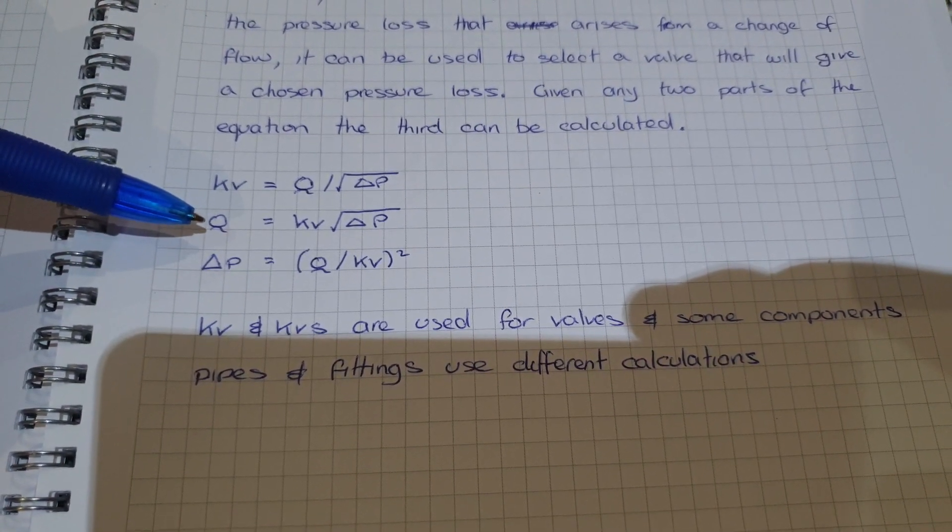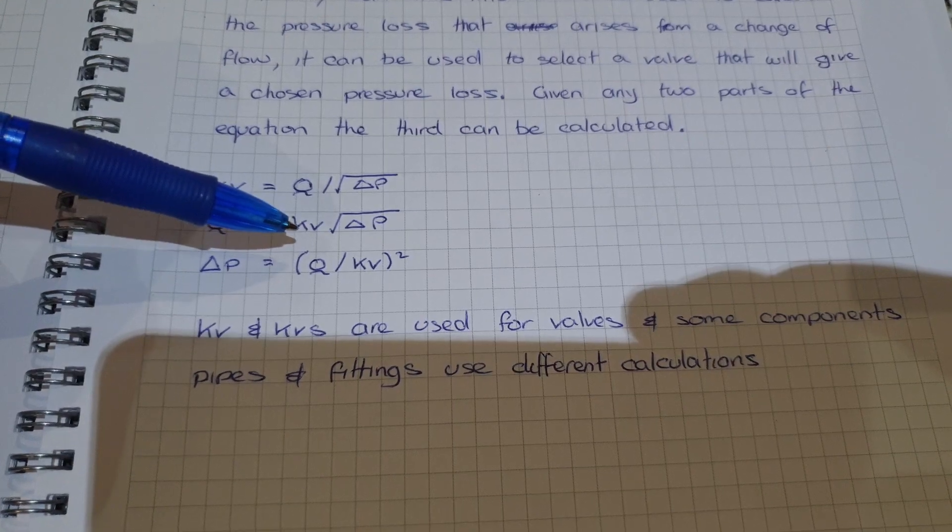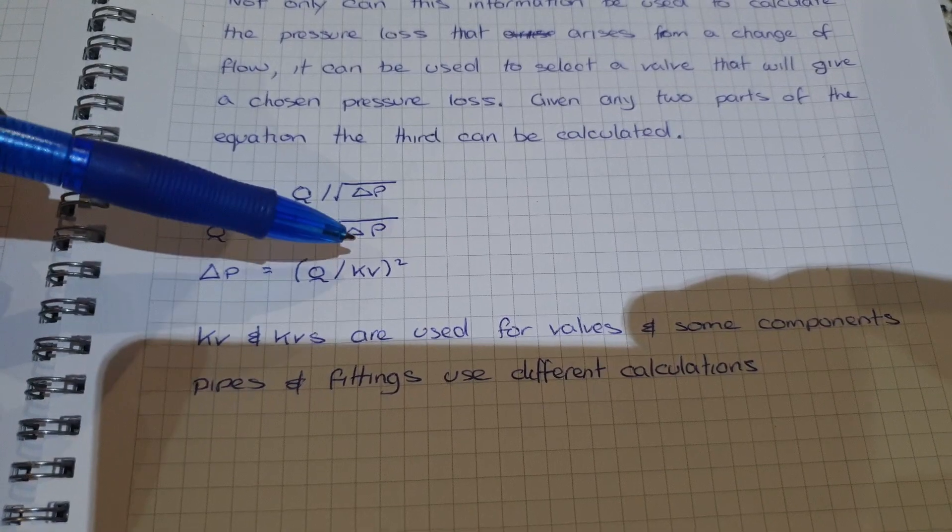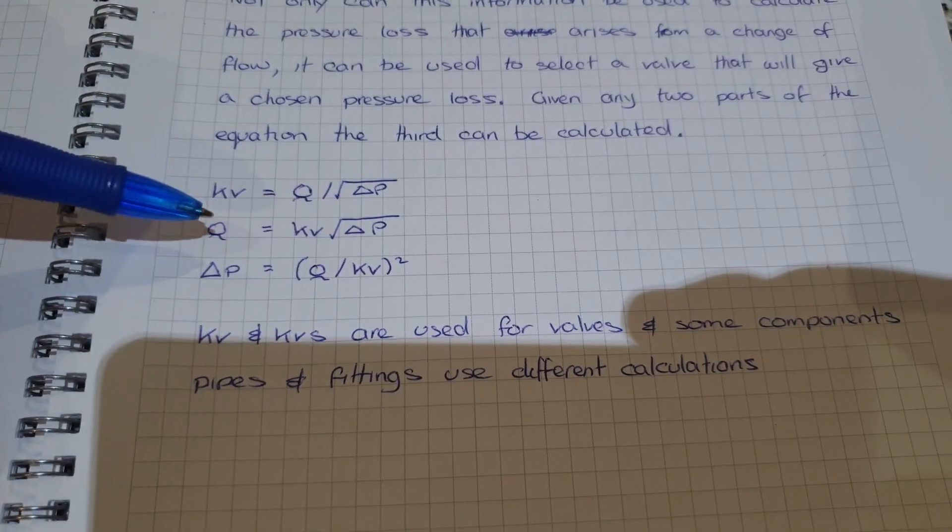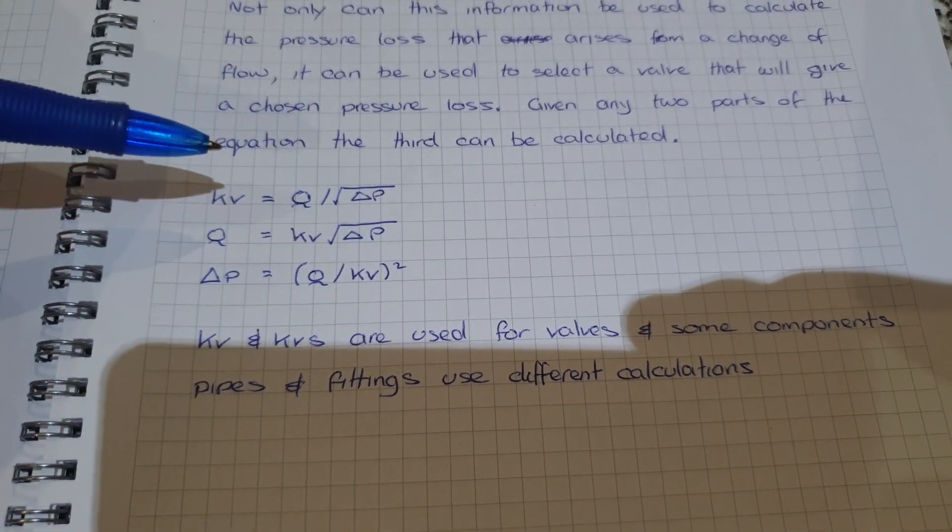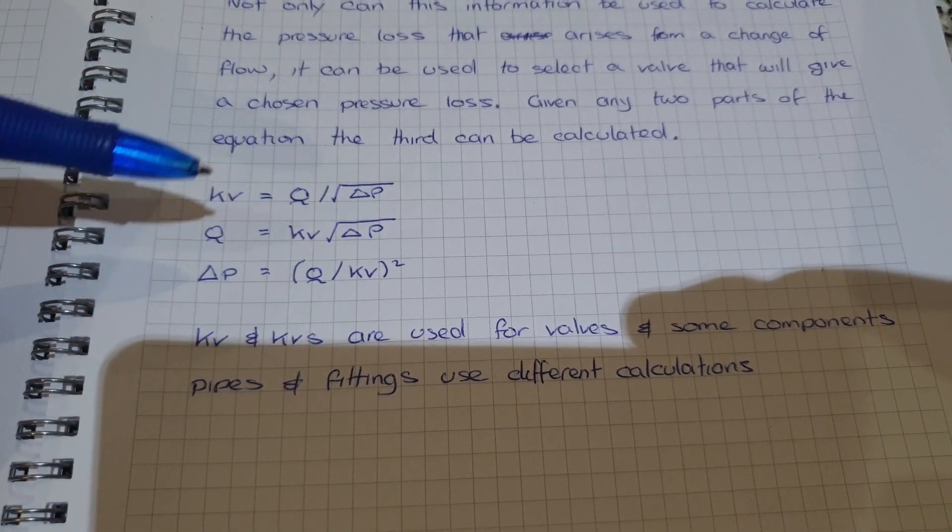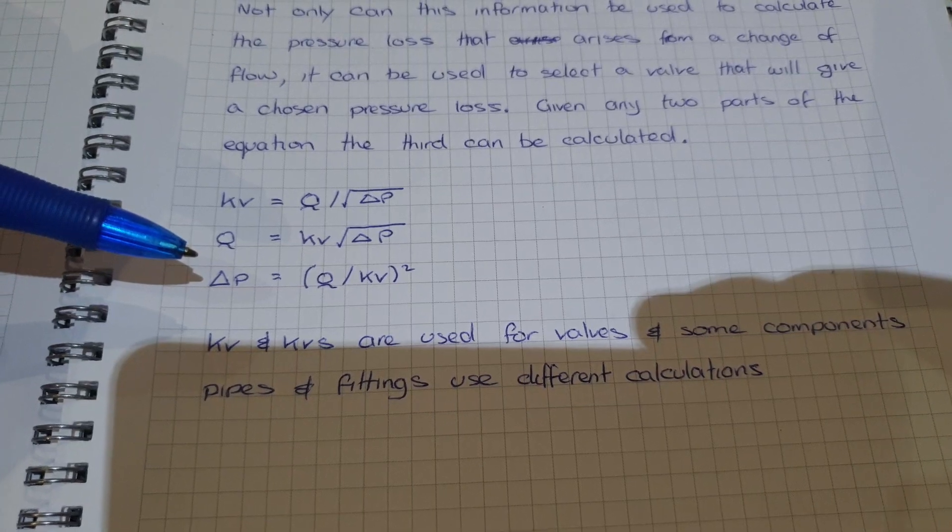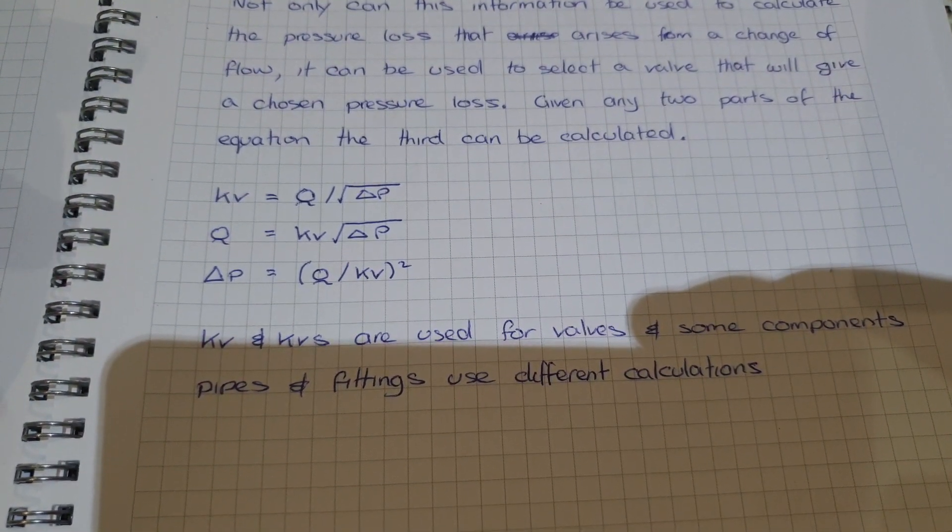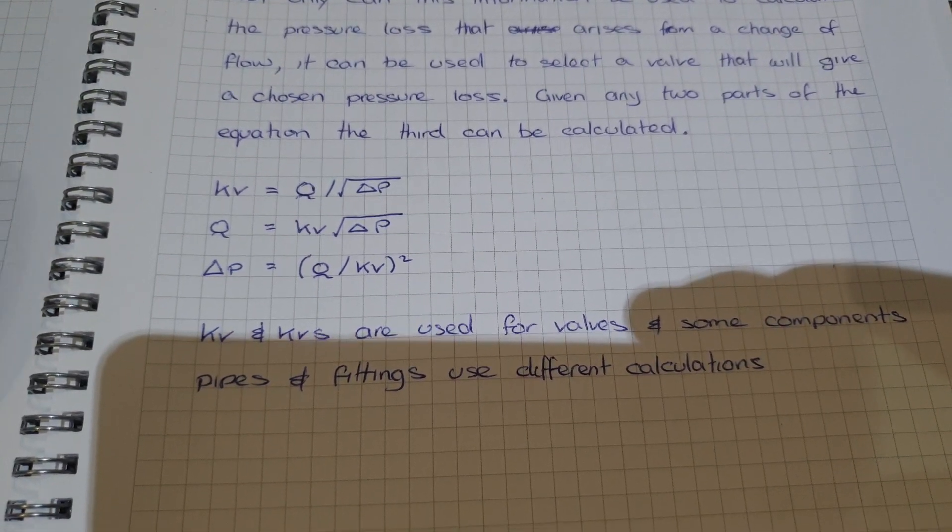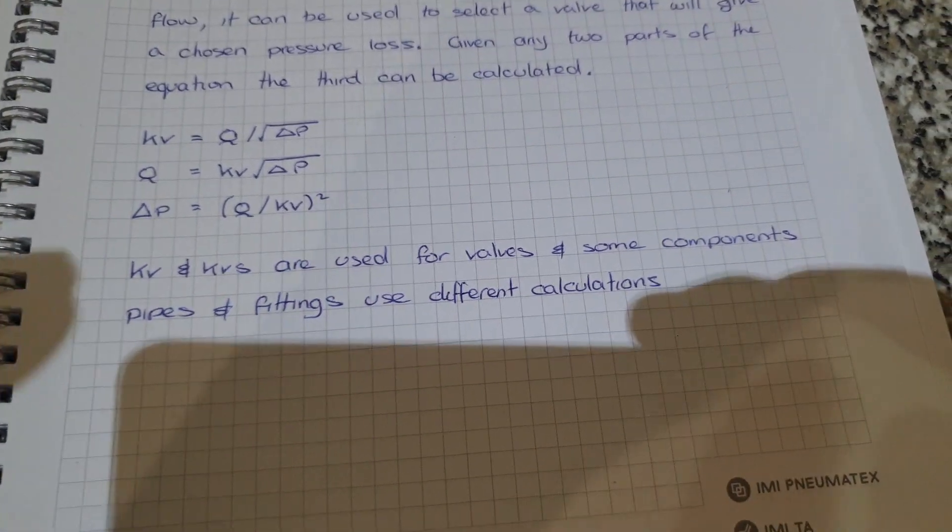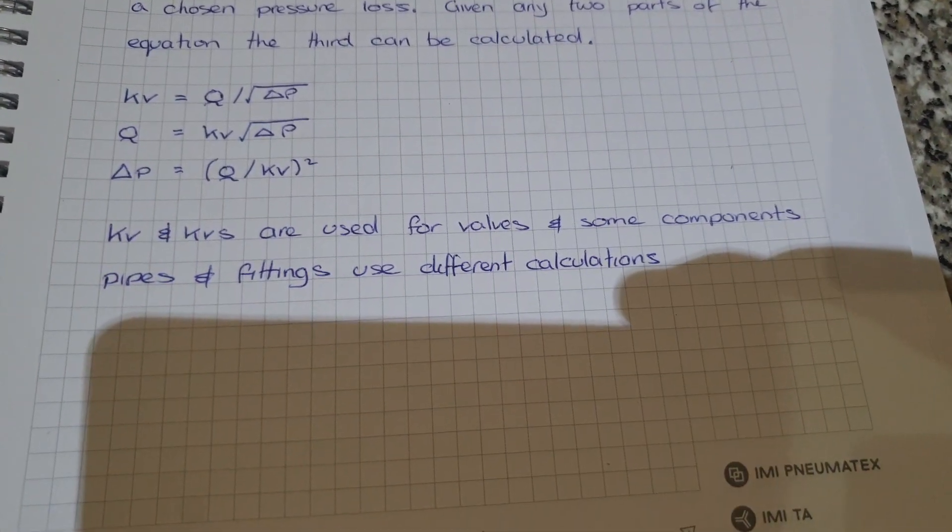If we wanted to know what the flow will be when we apply a valve of a given KV value, or we know the KV value and we change the flow, Q will equal the KV times the square root of delta P. And the other side of this: if we want to know what the delta P will be, we've got Q divided by KV value squared.